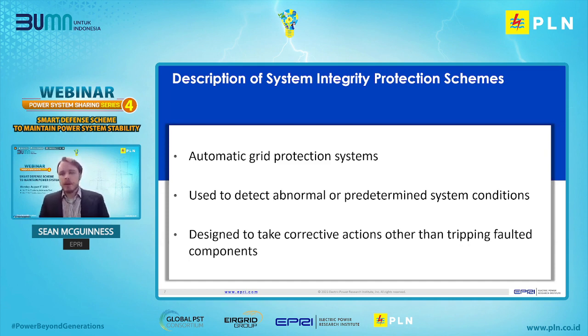As mentioned by the previous speaker, these defense schemes are typically automatic grid protection schemes, and they're used to detect abnormal or predetermined system conditions. In contrast to most protection systems which detect short circuit faults and isolate the faulted equipment, these take other corrective actions based on specific types of phenomena such as power swings, oscillations or overloads.